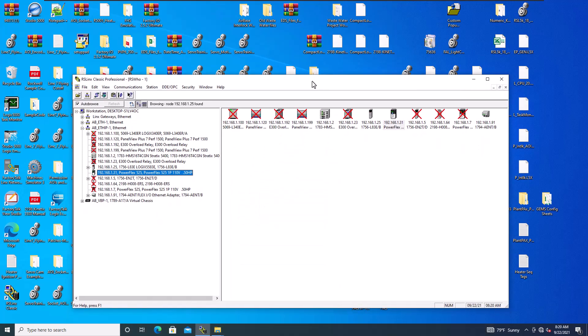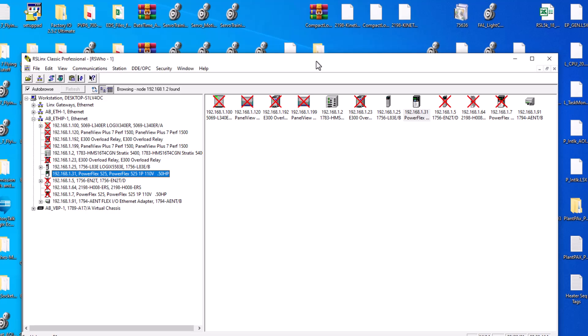Hopefully that was educational on how to download, upload, or update the firmware to a drive. You can do the same thing if you wanted to flash it backwards - you could flash it backwards if you wanted to. When it comes down to it, it depends on your situation: are you in a pharmaceutical environment that is highly regulated, or are you trying to push forward and make the drive more compatible with a different AOP or software - like making it compatible with version 33, 35, or even 36? This is a solid process on how to use ControlFlash to flash the firmware of a drive, at least the PowerFlex 525. Hopefully that was helpful and we'll see you guys on the next one.